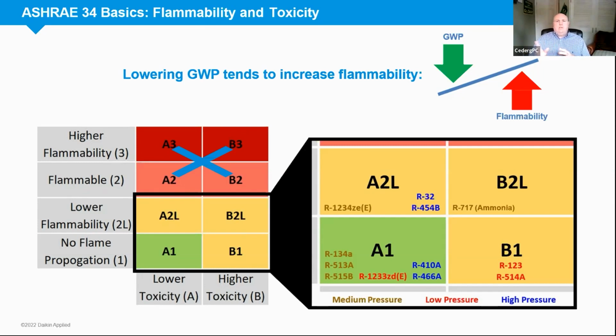I'll show you the reason why this is going to be important. One thing to understand: typically the lower the GWP, the higher the flammability. As you can see in the A1 category, R134a and R513A, but R410A and R134a—the two dominant refrigerants we're using—are all A1s. Moving forward, the two refrigerants we're looking at are R1234ze to replace R134a, and R32 to replace R410A.